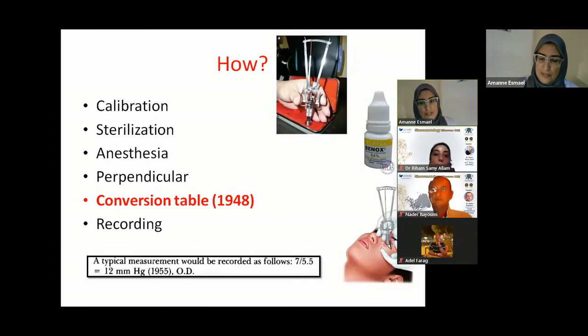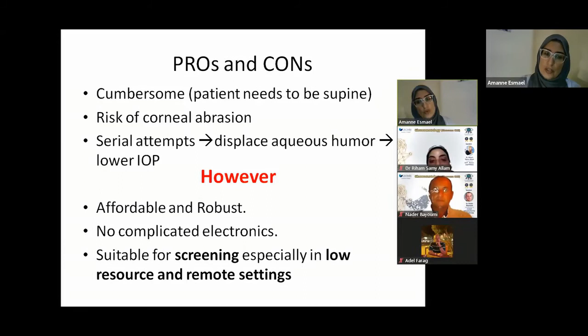Indentation tonometry by Schiotz could be considered cumbersome by some, as the patient needs to lie supine. There is a risk of corneal abrasion if the patient moves and doesn't stay still. And serial attempts displace aqueous humor and may cause a falsely lower reading. However, we should not forget that the Schiotz tonometer is affordable and robust. It doesn't have any complicated electronics involved. It is suitable for screening, especially in low resource areas and remote settings.